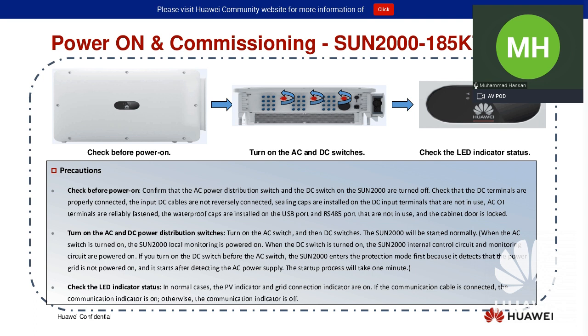Then the second thing is you need to power on the AC switches first, and then the DC switches. The correct procedure for turning on the SUN2000, or any inverter, is to turn on the AC first, and then the DC. Once you turn on the DC, the inverter starts operating normally, the LEDs start blinking within a couple of seconds, and then you will be able to do the commissioning of that inverter. If you turn on the DC first, then the inverter will wait for the AC supply, no grid will be available, and it will start the process again and again. So it's always recommended to switch on the AC first and then the DC, so that the inverter follows the proper procedure.